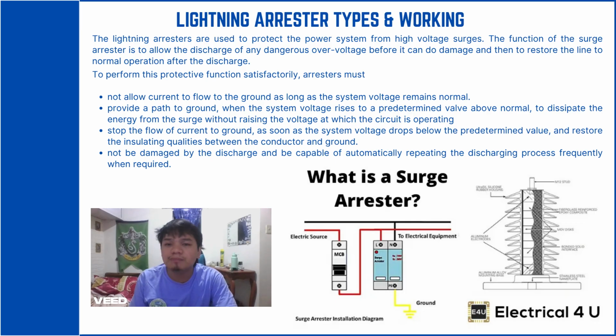So to perform this protective function properly, a lightning arrestor must have the following characteristics. First, it should not allow any current to flow to the ground as long as the system voltage is normal. Second, when the voltage rises above a certain predetermined level, the arrestor should quickly provide a path to the ground, allowing the surge energy to dissipate safely. And the third one, once the voltage returns to normal, it should immediately stop the current and restore the insulating properties between the conductor and the ground. And lastly, the arrestor must not be damaged by the discharge and should be capable of repeating the process automatically whenever needed. So, in summary, the lightning arrestor acts like a protector of the electrical system, staying inactive during normal operation, but reacting instantly to any voltage or lightning surge to keep the equipment safe.